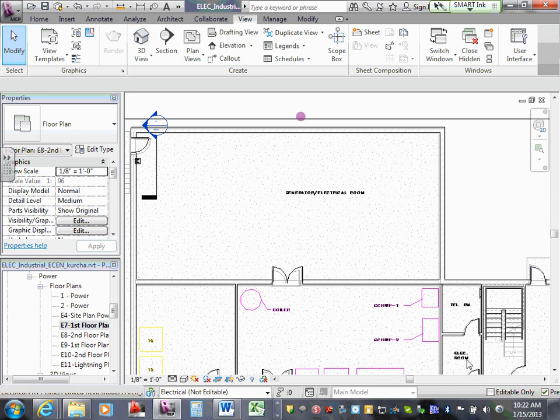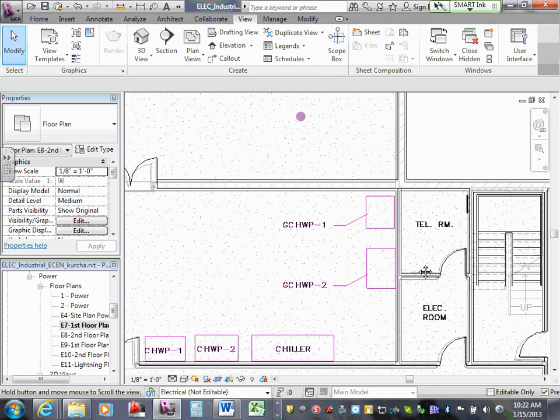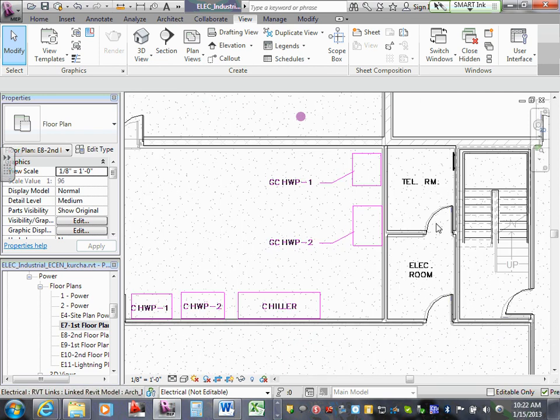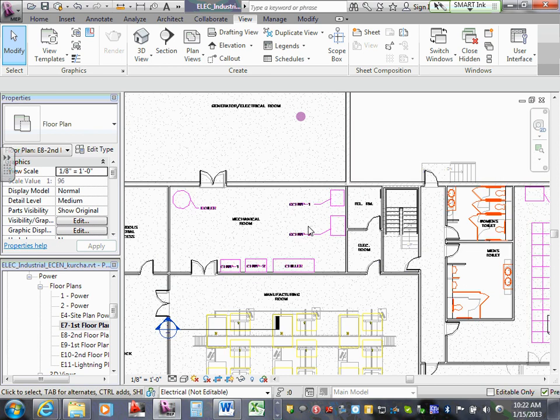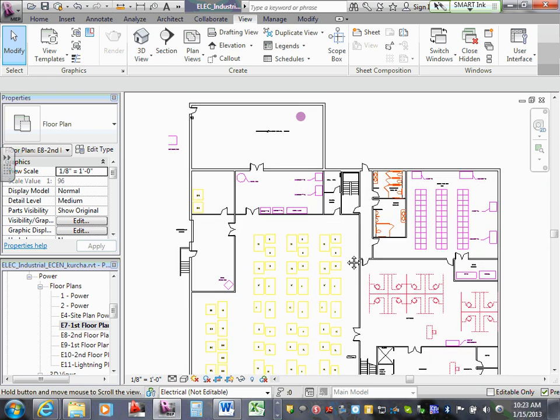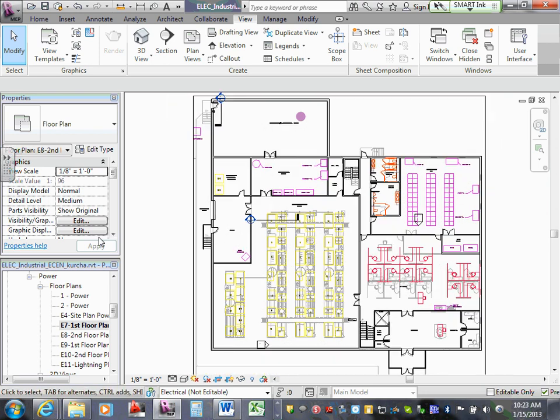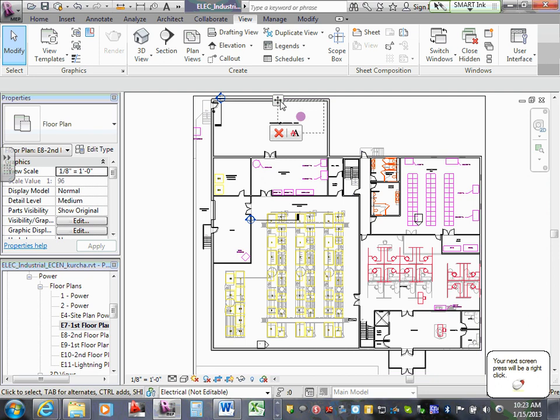Fire alarm panel is most likely going to go in the electrical room, or telephone room, or within the electrical generator room, somewhere close to the telephone lines for the dialer. Depending on the size of the system, there are different sizes of the building and number of devices required. There are different sizes of panels that you can get. You got panels that'll handle 100 points, panels that'll handle 320 points, all the way up to panels that'll handle 2,000 points and can be networked up to 20,000 points.